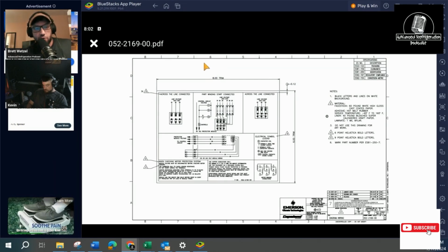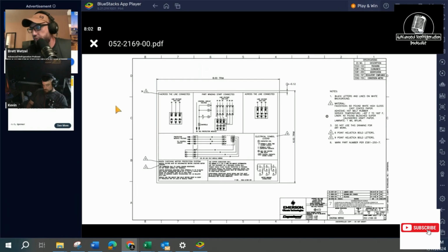On some scrolls you have a sight glass, and sometimes the sight glasses leak after years or even a gas change out. They'll actually label all the gaskets that go with that particular compressor, plus some of the other components.